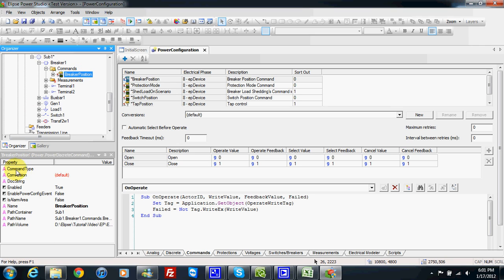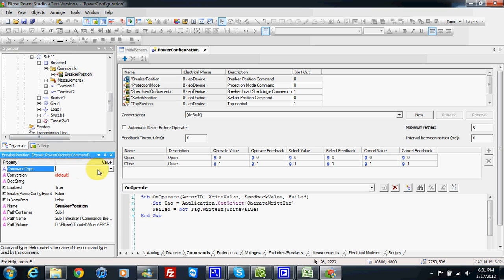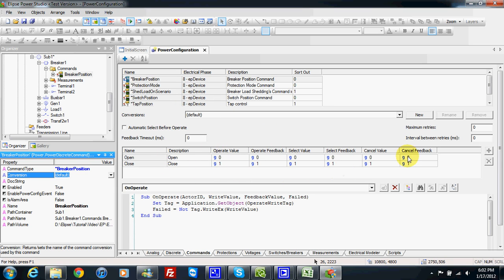In my breaker position, in the property, I have to tell the system this breaker position is a breaker position command type. As mentioned previously, we can apply a conversion. If the relay we are using is from ABB, we use the values designed by ABB. If we have a relay made by AREVA, we have to apply another conversion and use the values designed by AREVA relay for all the select, operate, and cancel operations, according to the protocol we are using. According to protocol and equipment, we can use different conversions, and we can select the proper conversion for this specific equipment.